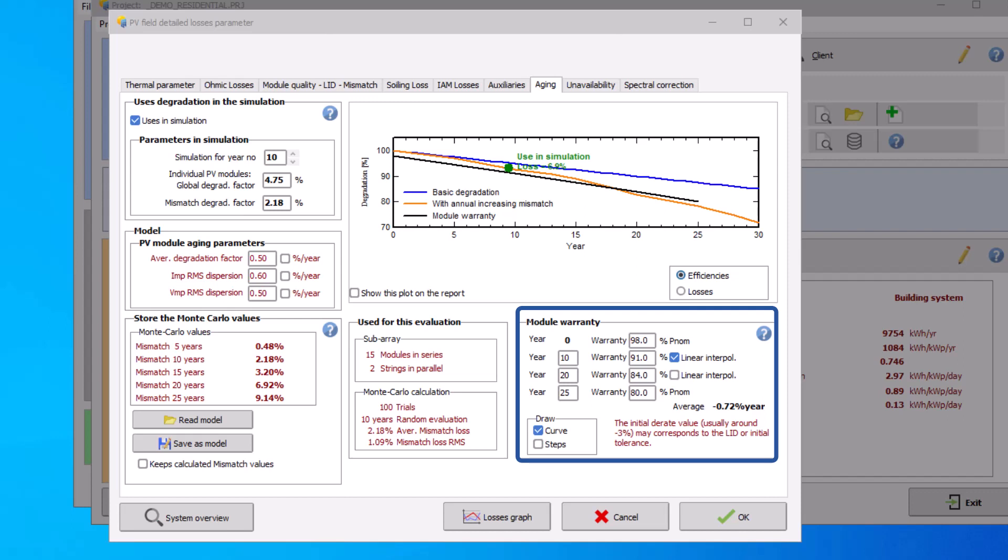PVSYST pre-fills the fields with fixed default values, and you should verify that these correspond to the PV modules you will be using. This value should be understood as the worst case degradation for an individual PV module, and should not be confused with the degradation rate of the PV system.